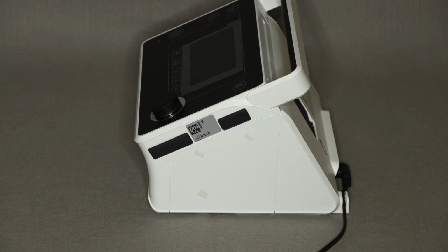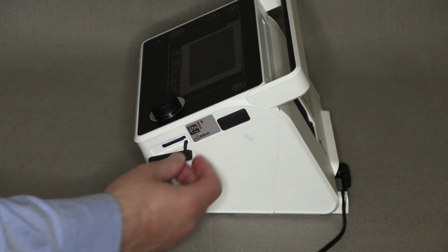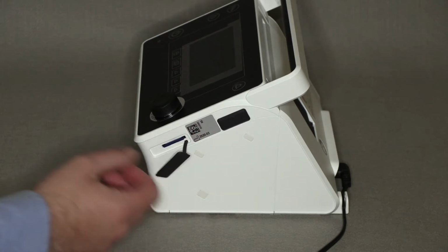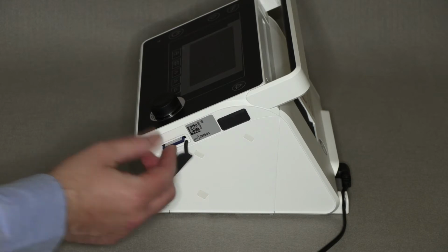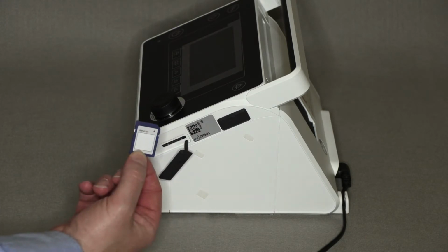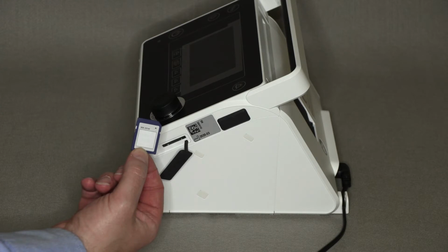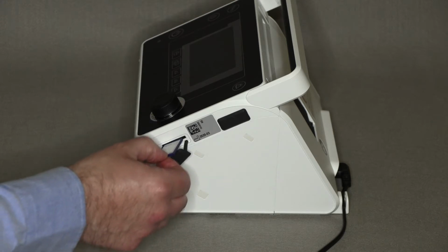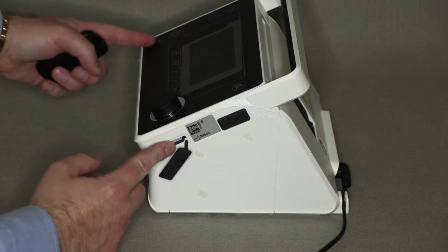On the right hand side of prismaVENT there is a rubber plug. When this plug is removed, you will expose the back of an SD card which will contain all usage information from the device. When prismaVENT is turned off, you can press this SD card to eject it. You can now send the SD card wherever you need to send it. And don't worry, you can continue to use the ventilator even when there's no SD card inside.